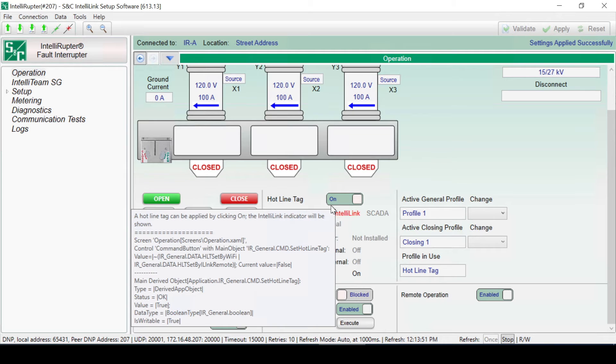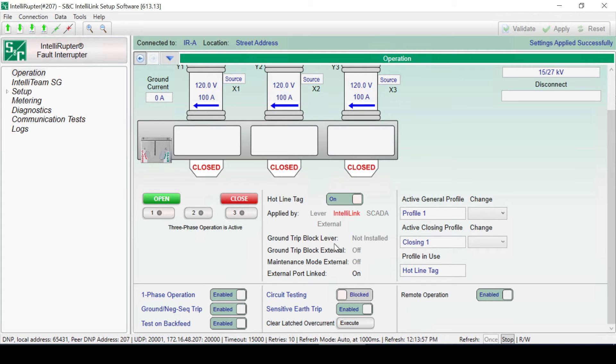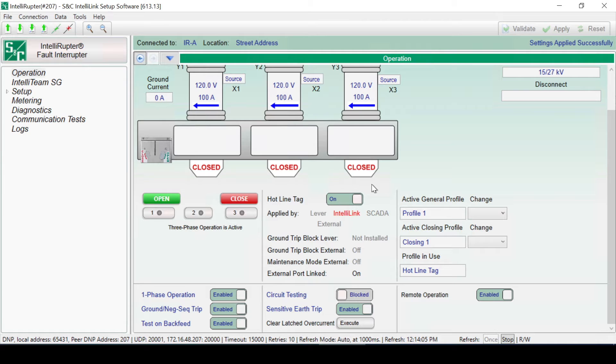When applied, the IntelliLink text will turn red. The fault interrupter will not close while a hotline tag is enabled, but it can be opened through any means. If a hotline tag was applied locally on the fault interrupter or via SCADA, the associated text will turn red as well.